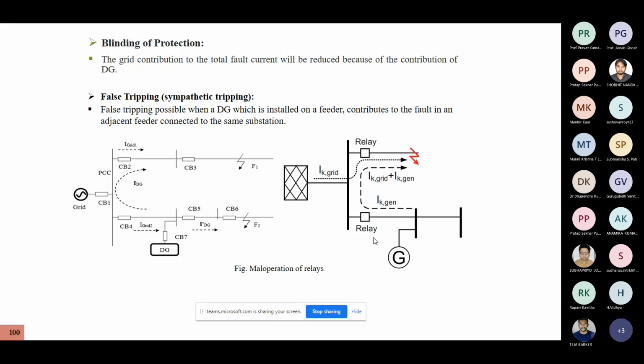You are taking TDS, your PSM, you are selecting the primary and backup pair. Accordingly, you are formulating the objective function, and you are making the total operating time minimum. But now with the inclusion of the DG, we take a specific curve. With the inclusion of DG, there is a possibility of augmentation of the objective function, because your CTI should not get violated.